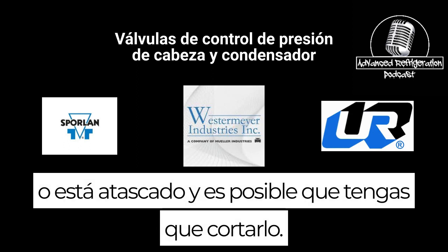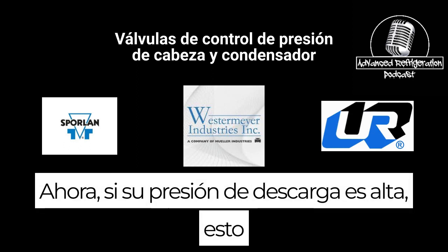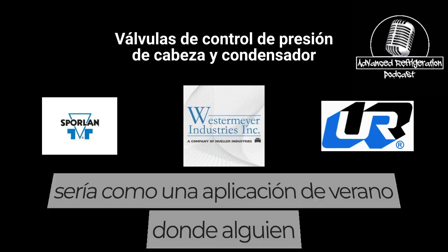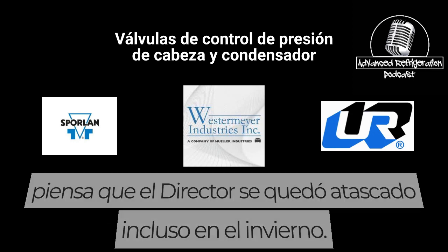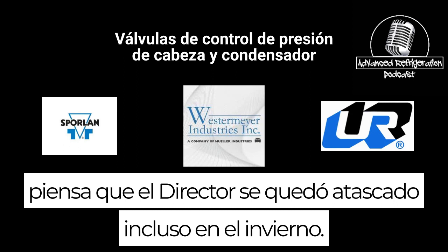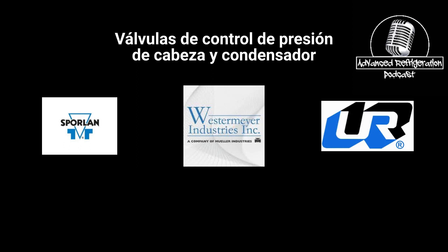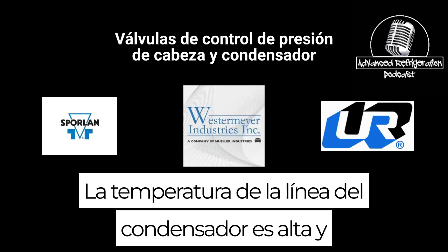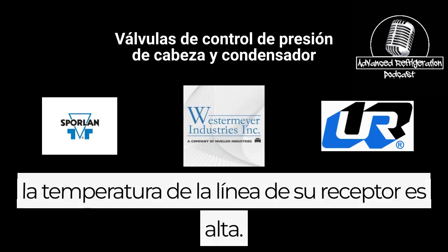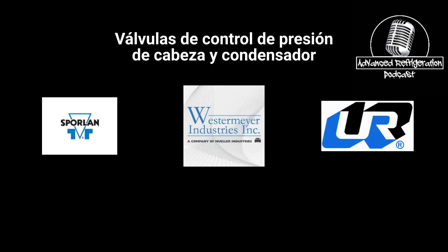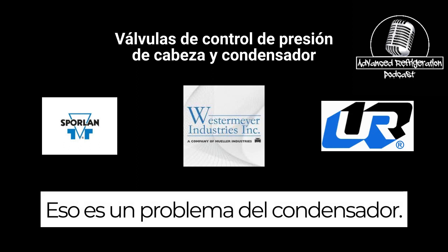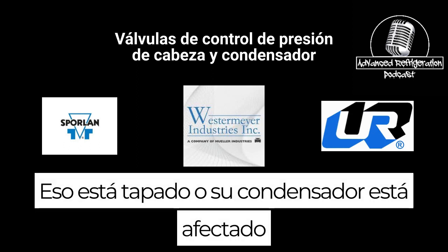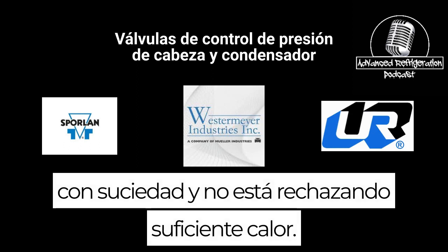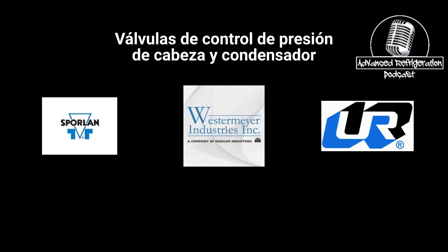or it's stuck and you may have to cut it out. Now, if your discharge pressure is high, and this would be like a summertime application where somebody thinks the headmaster's stuck, and even in the winter your condenser line temperature is high and your receiver line temperature is high, that is a condenser issue. It's either plugged or your condenser is impacted with dirt and you're not rejecting enough heat.